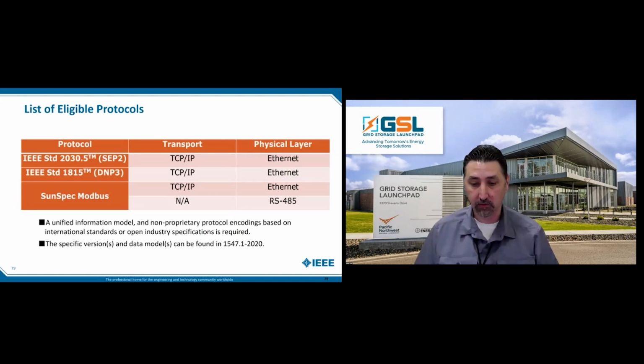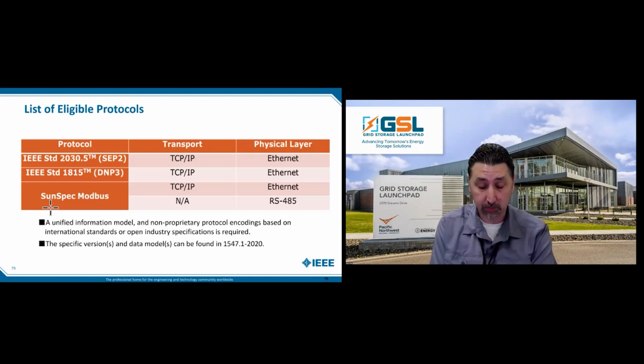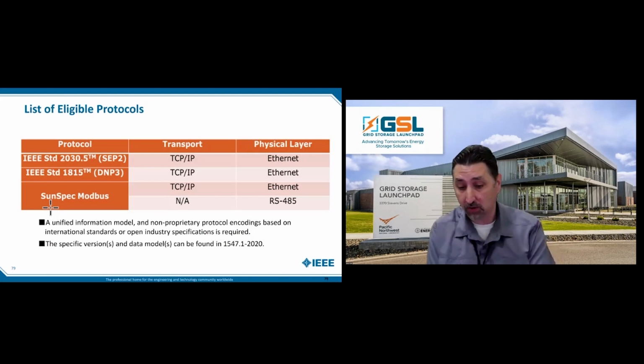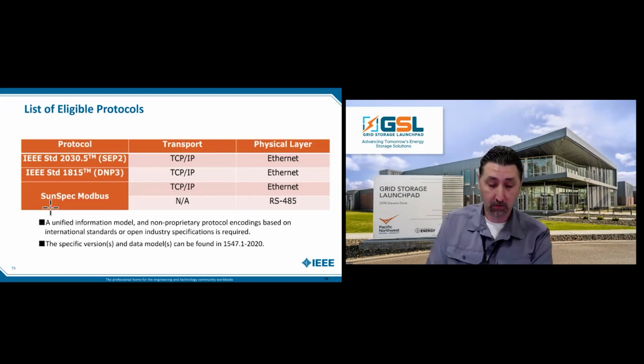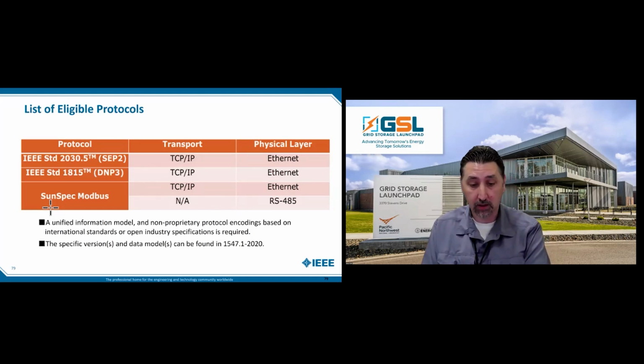Specifically in the most current version of 1547, this is the 700 series inverter data model that's called out, and it's not the entire model. I've got another presentation where we can talk about some of the things that are left out of 1547, like energy storage. But specifically, there is a set in 1547.1 of the list of data objects that are mandatory and optional. So definitely suggest that as a companion to any 1547 specification, you would also look at the .1, the test procedure, to make sure that you're getting all the right data objects that are defined.